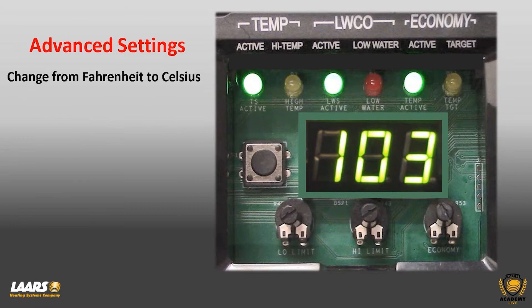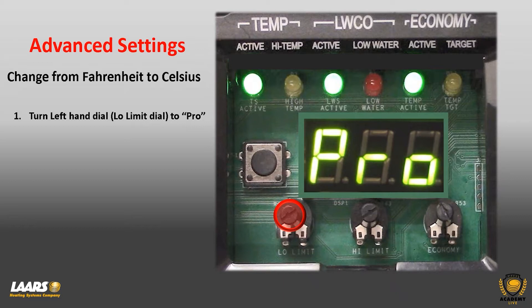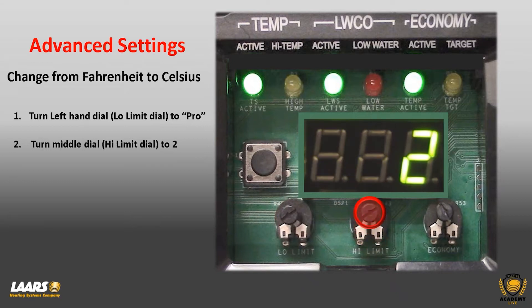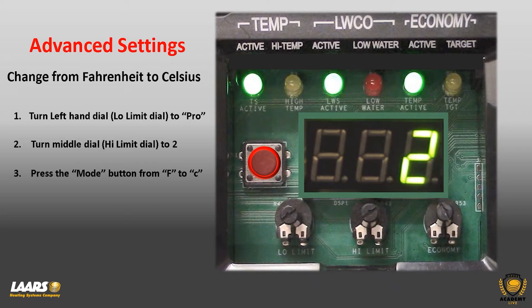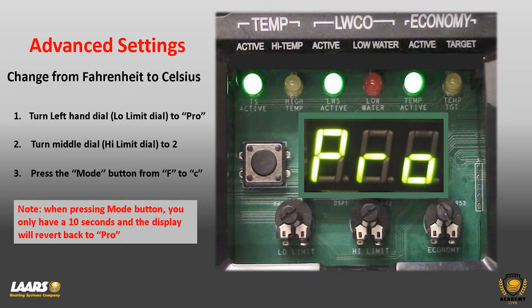To change from Fahrenheit to Celsius, start with the left-hand dial and turn it until you see the letters PRO for programming on the display. Next, choose the middle dial and turn it to the number two. Now use the mode button — caution: if it sits idle for 10 seconds it will revert back to PRO. Press it once and you'll see the letter F for Fahrenheit; press it a second time and you'll see lowercase C for Celsius. Be patient and it will revert back to programming in 10 seconds.